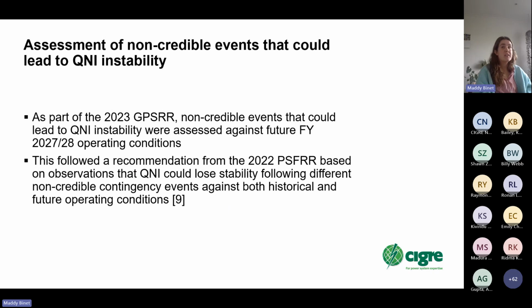As part of the 2023 General Power System Risk Review, we looked at different non-credible contingency events across the NEM that could lead to QNI instability for future operating conditions, 5 years ahead, looking at financial year 2027-28. This followed on from a recommendation from the 2022 Power System Frequency Risk Review, based on observations that QNI could lose stability following different non-credible contingency events under both historical and future operating conditions.